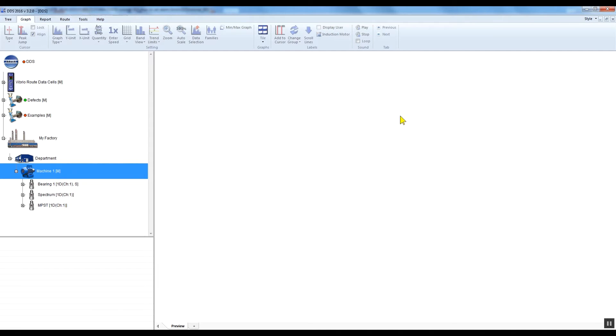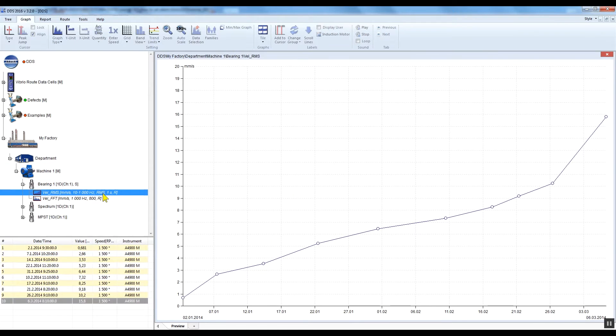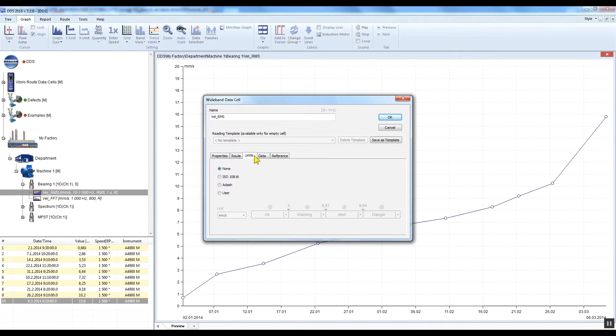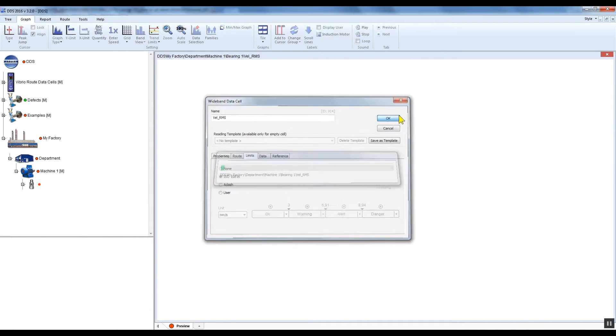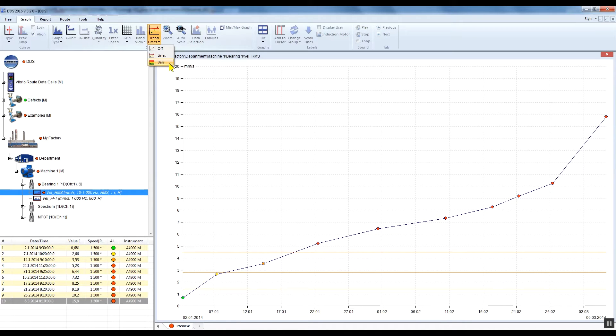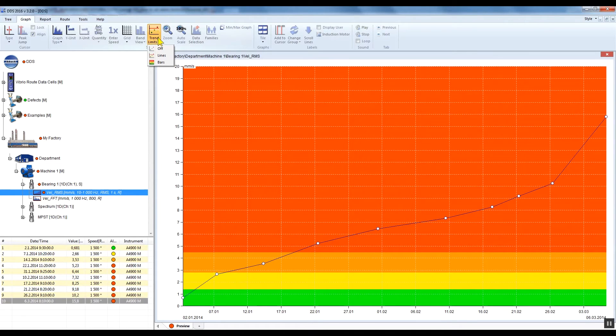ISO 10816 standards are applicable only for velocity RMS data cells with a 10 to 1000 Hz range. Right-click on that data cell and select Properties. Go to the Limit tab, click ISO 10816, and confirm by clicking OK. You can see that individual measurements have changed colour according to the applied limits. You can change the appearance of limits — go to the graph tab and click on the Trend Limits button to see lines or bars.